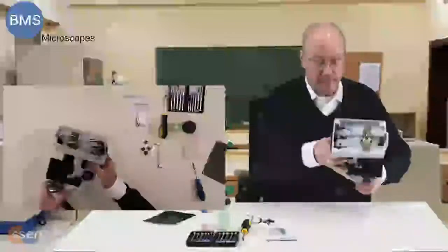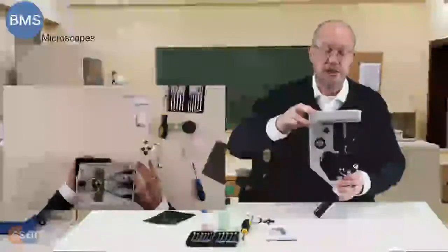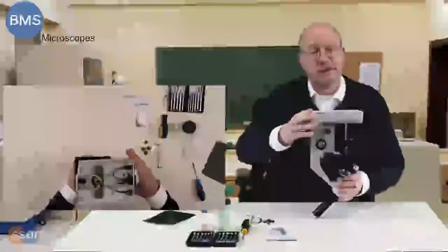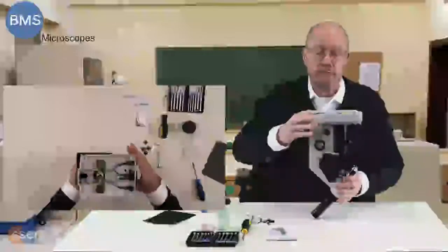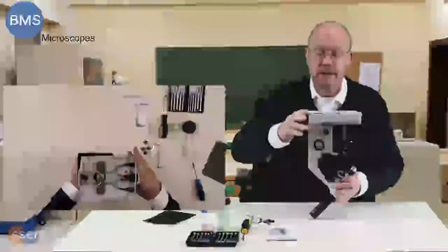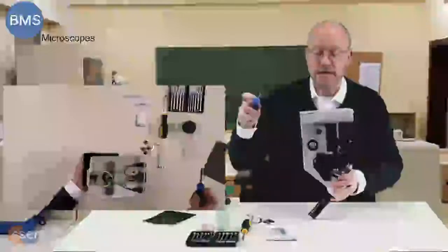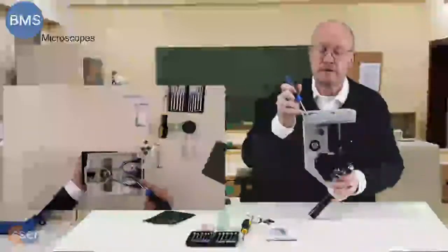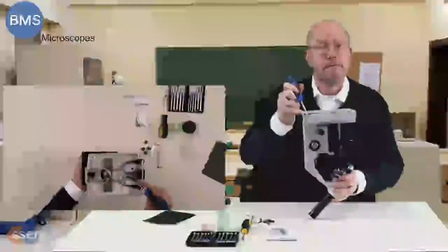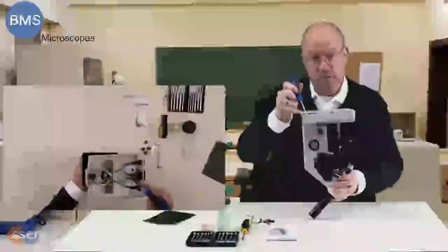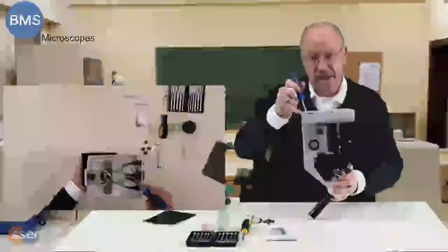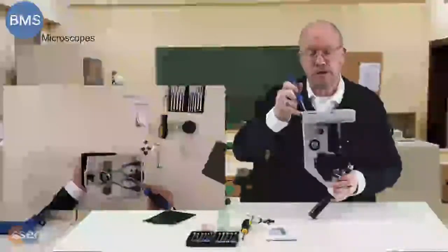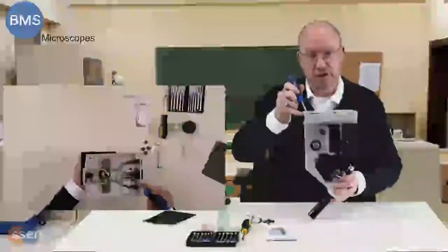Bottom plate. You look inside the microscope now. You will see the wiring. Depends on, of course, the microscope that you have there. What's very important is to see if there is an earth connected cable. You have to undo that, but you have to place that connection exactly back on the same place again. Make sure you make a note of that also.